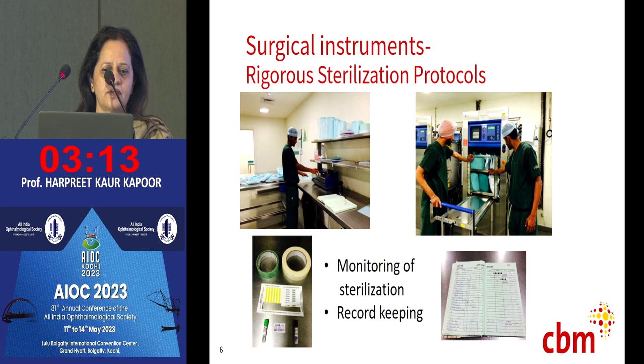So have so many sets that you don't have to use instruments by just dipping them in some solution or something like that. Besides the autoclaving or sterilization process, it is also mandatory to monitor the sterilization with chemical and biological indicators, and record keeping is utmost.